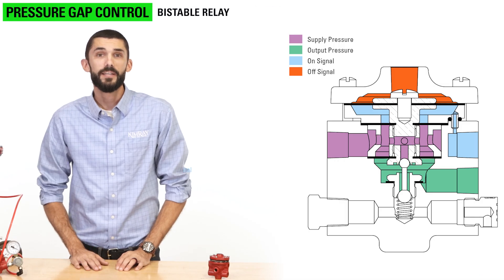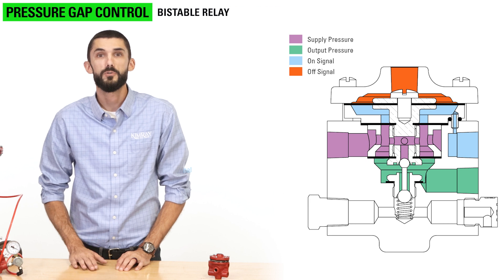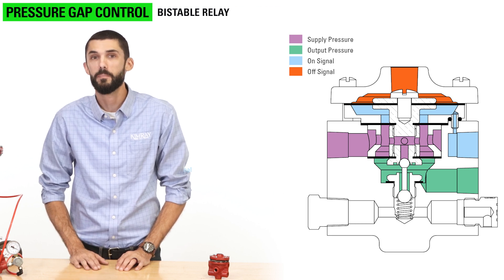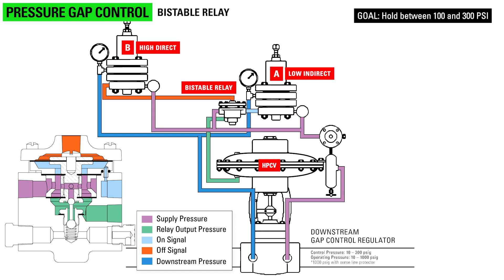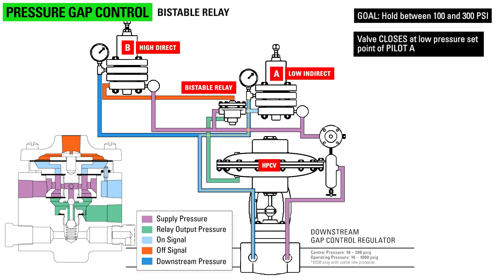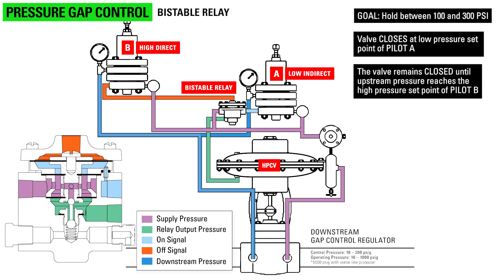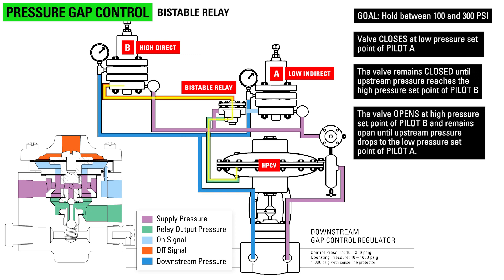If you need to pneumatically control pressure range or gap, you can use the bistable pneumatic relay with two pneumatic pilots. The pressure will fluctuate between the two set points of the pilots. For example, say you want a high pressure control valve to hold pressure between 100 and 300 psi. The high pressure control valve closes at the low pressure set point of pilot A. The valve remains closed until upstream pressure reaches the high pressure set point of pilot B. The valve opens at the high pressure set point of pilot B and remains open until the upstream pressure drops below the low pressure set point of pilot A.